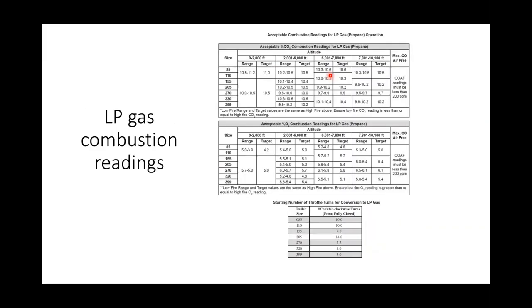LP will not be found in the I&O manual. It would be found in the sheets included with the LP conversion kit. And if it's LP, you would need to be in these ranges. And again, the approximate throttle screws to get the unit to fire. Now, these are just approximate. They're not going to be the dead final numbers. But make sure it's burning in its proper ranges and you got good light off.